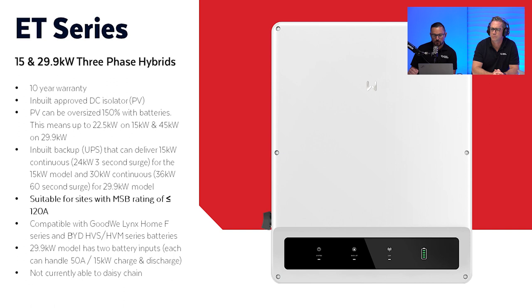One of the most impressive aspects, especially of the larger 29.9 kilowatt model, is that it can achieve pretty impressive backup abilities. Basically 10 kilowatt per phase of backup potential, and it has a small surge at 36 kilowatt three phase for up to 60 seconds.